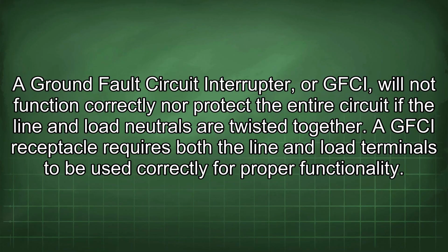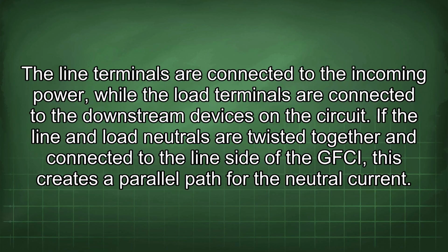A ground fault circuit interrupter, or GFCI, will not function correctly nor protect the entire circuit if the line and load neutrals are twisted together. A GFCI receptacle requires both the line and load terminals to be used correctly for proper functionality. The line terminals are connected to the incoming power, while the load terminals are connected to the downstream devices on the circuit. If the line and load neutrals are twisted together and connected to the line side of the GFCI, this creates a parallel path for the neutral current.